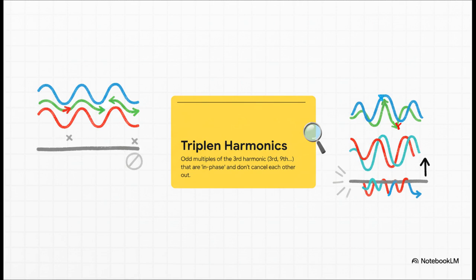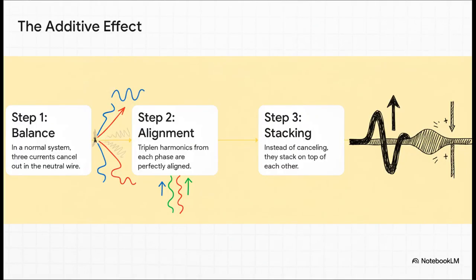But triplen harmonics throw a giant wrench into the whole thing. Because of their specific frequency, they're all in phase, meaning they don't cancel each other out. They all line up perfectly. Instead of canceling out and leaving that neutral wire with basically zero current, these triplen harmonic currents from all three phases just stack, piling on top of each other, adding up in the one wire that's supposed to be carrying almost no current at all.